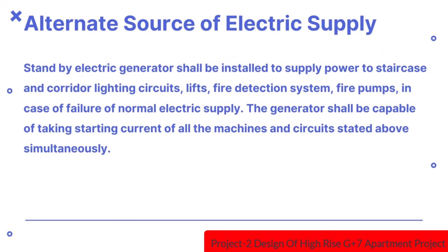Regarding alternate source of electric supply: a standby electric generator shall be installed to supply power to staircase and corridor lighting circuits, lifts, fire detection system, and fire pumps in case of failure of normal electric supply. The generator shall be capable of taking starting current of all the machines and circuits stated above simultaneously.